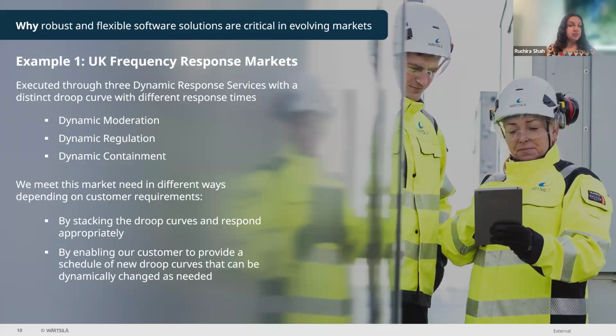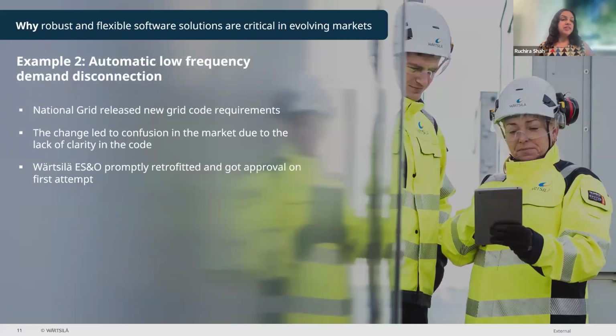So my second example is in the case of automatic low frequency demand disconnection. National Grid released new grid code requirements. Essentially, when you are importing, so when you're a battery and you're charging, and say the frequency happens to be below 50, so let's say it's 49.5, you need to essentially slow your charging according to the droop curve.